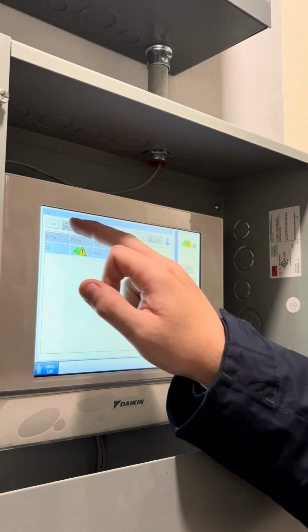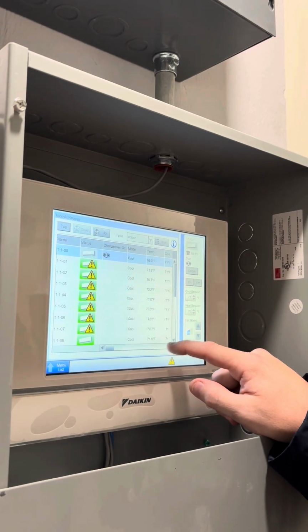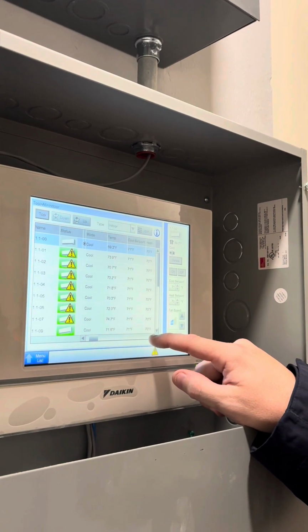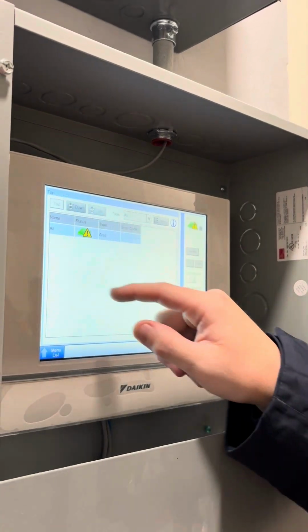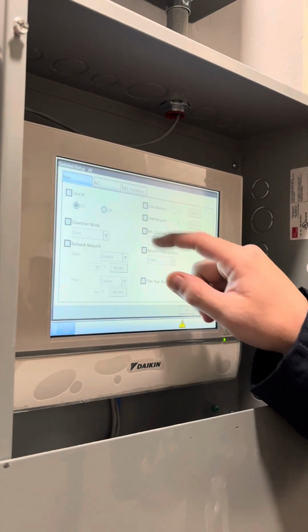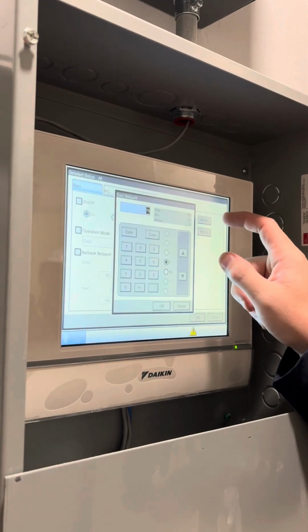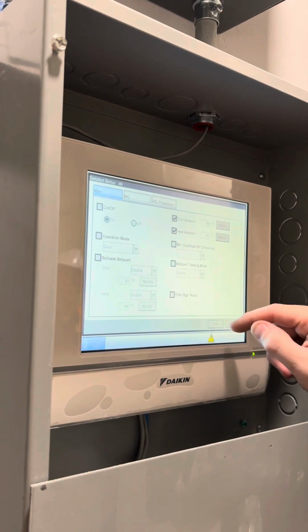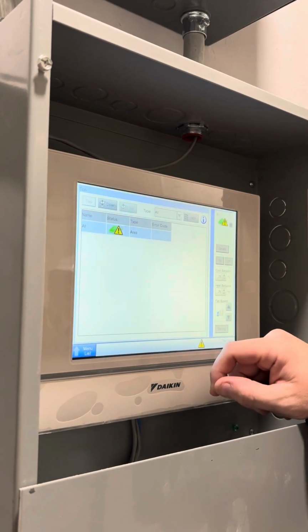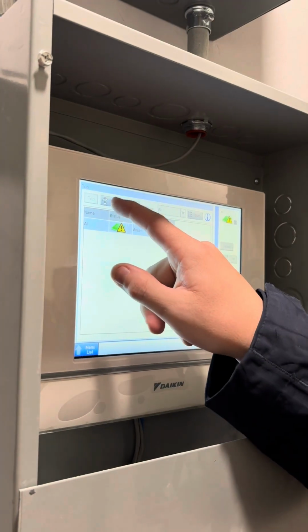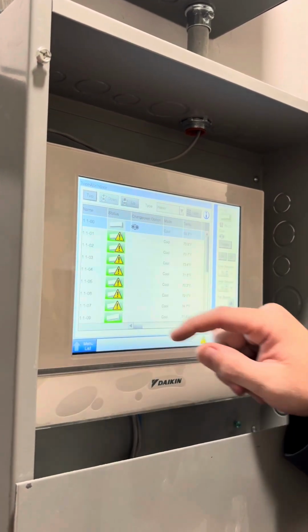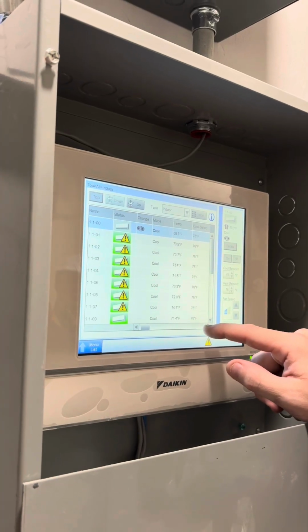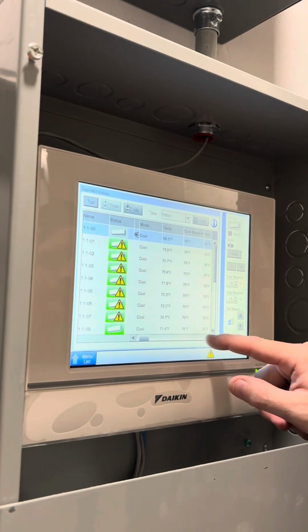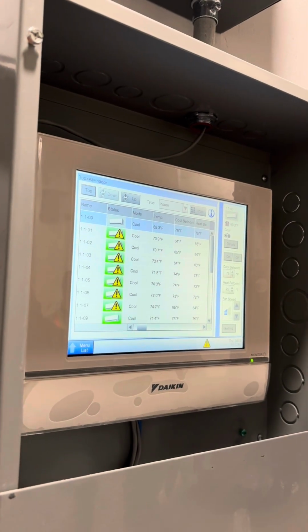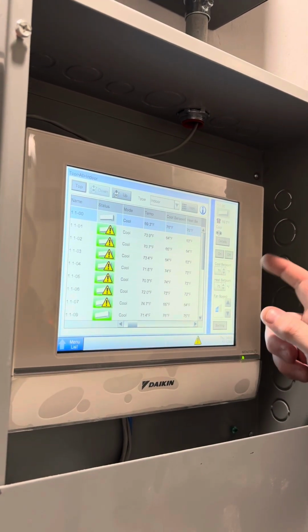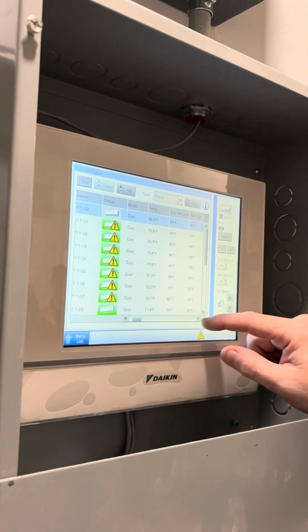We go through, and then what we should see is a cooling set point of 71, a heating set point of 70. Oh, I think it changed on me here, sorry. There, now we've got a cooling set point for all of them of 76 and a heating set point of 75, because it's doing that 1 degree deadband. So if you want more degrees of deadband, you can always change it in there.